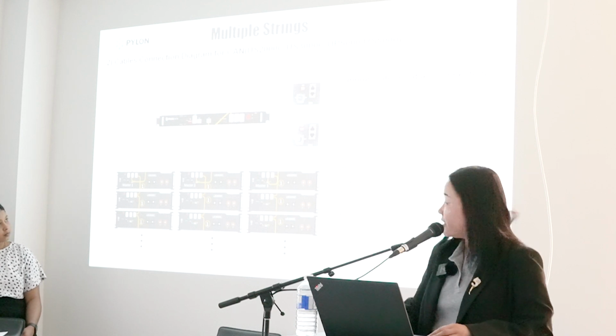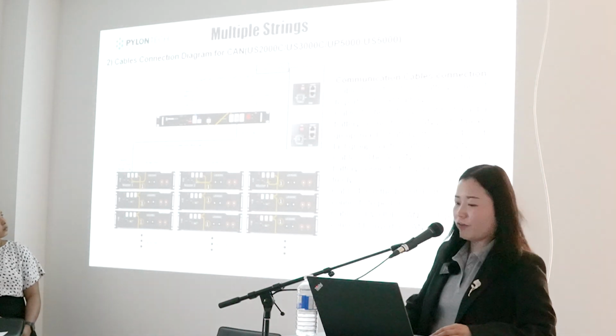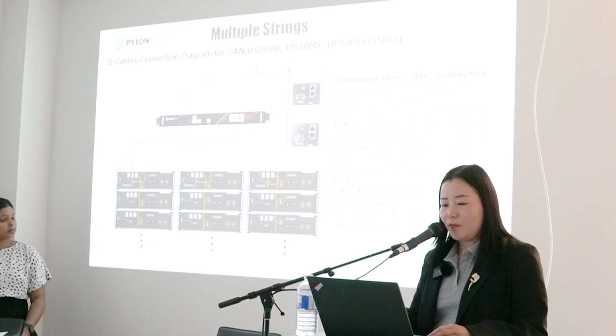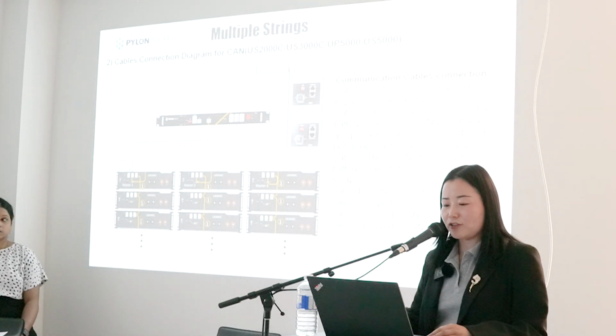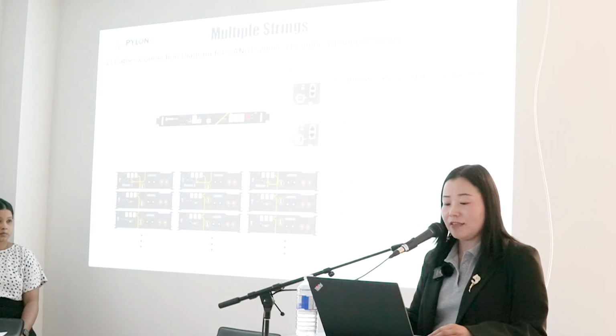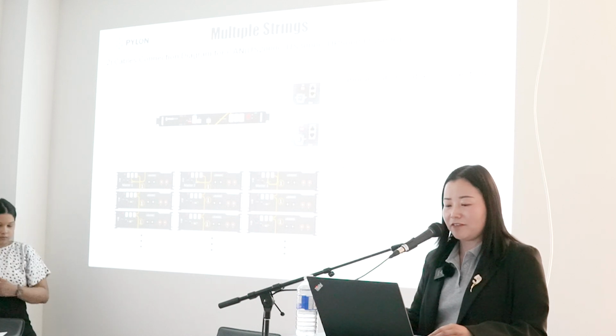Here it says the communication cables connection, cable 1, 2, 3, 4. You can see there are numbers on the cables, 1, 2, 3, 4. Cable 1, port 1 of the first battery connects to port 0 of the next battery. Cable 2, the RS485 port of the first master battery connects to the CAN port of the next group master battery. The RS485 of the last group master battery is empty.